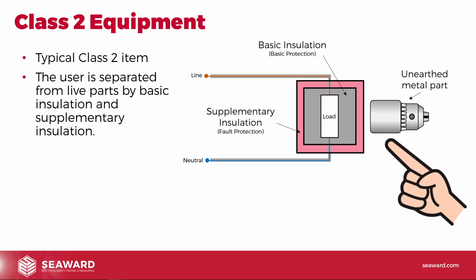So we've got the grey basic insulation, and then if something goes wrong with that, we've got the second layer of supplementary insulation. Our basic insulation provides the basic protection. The supplementary insulation provides the fault protection. So instead of Class 1 equipment, where fault protection was provided by earthing metal parts, in this case we don't earth the metal parts, we just use more insulation. If anything goes wrong with the basic insulation, we've got even more insulation there.